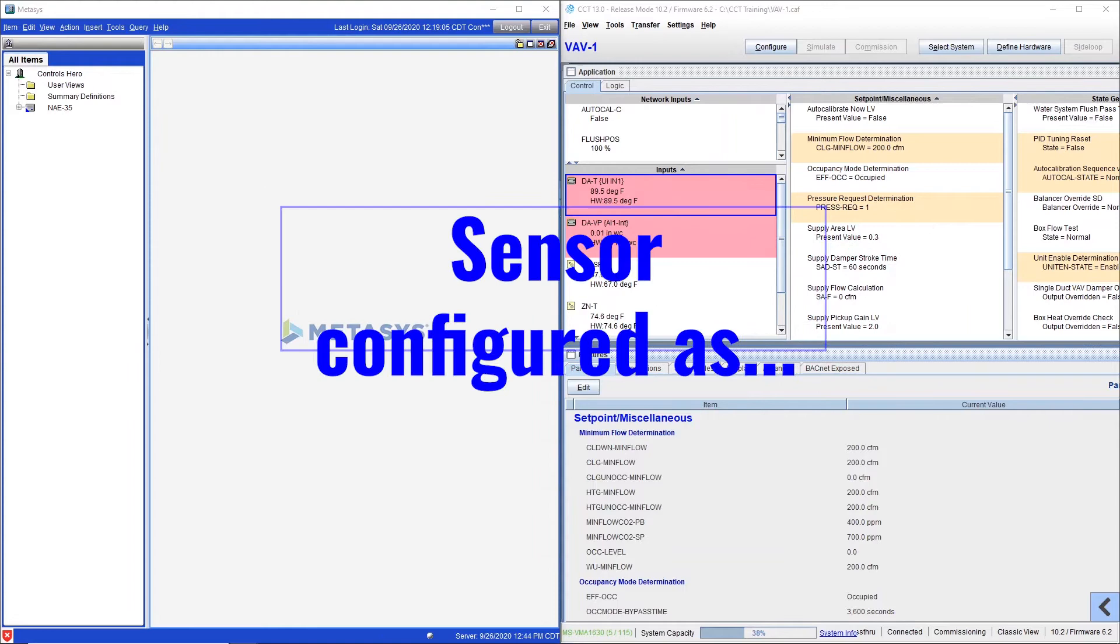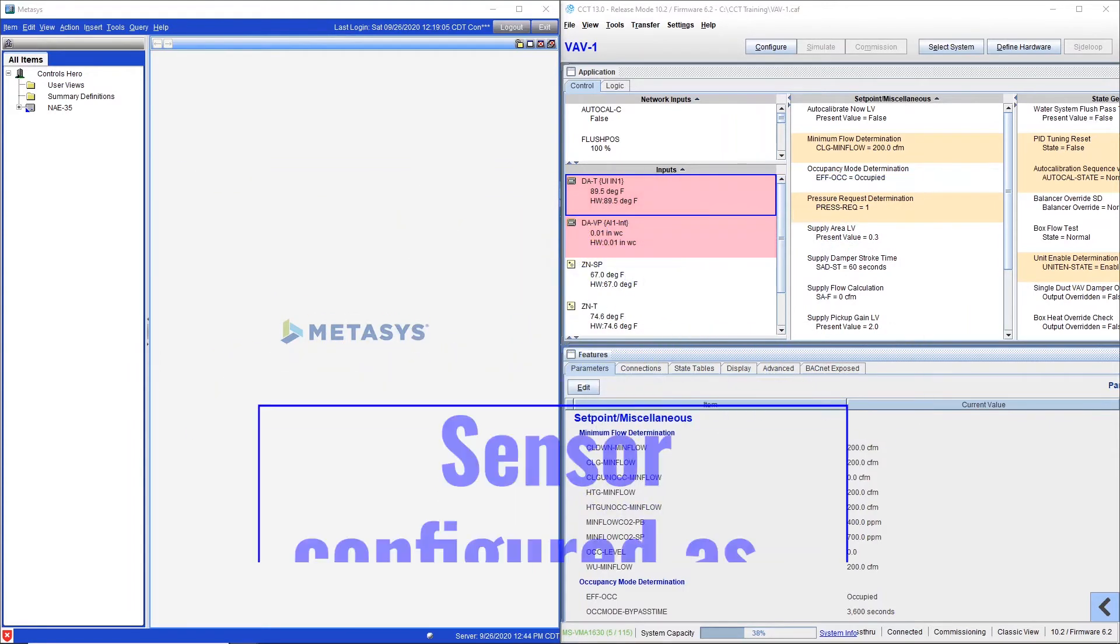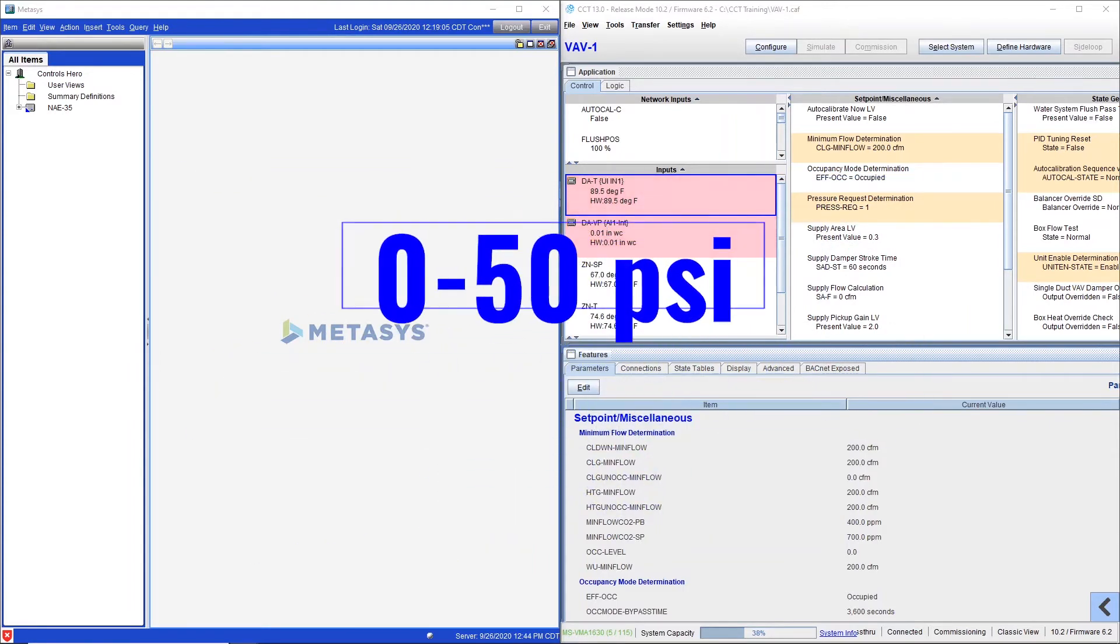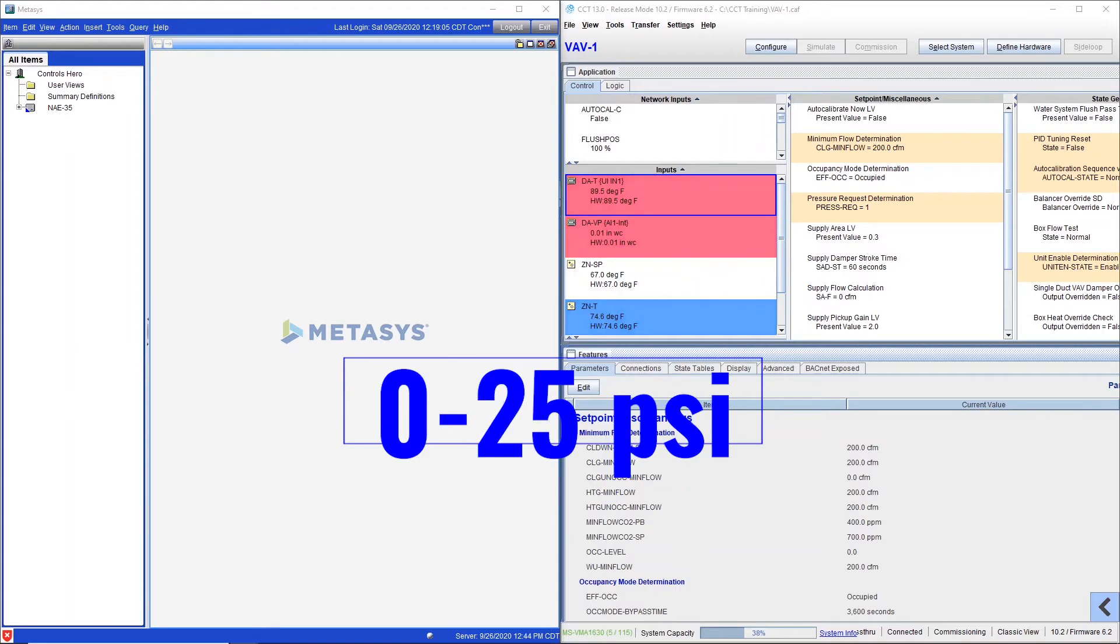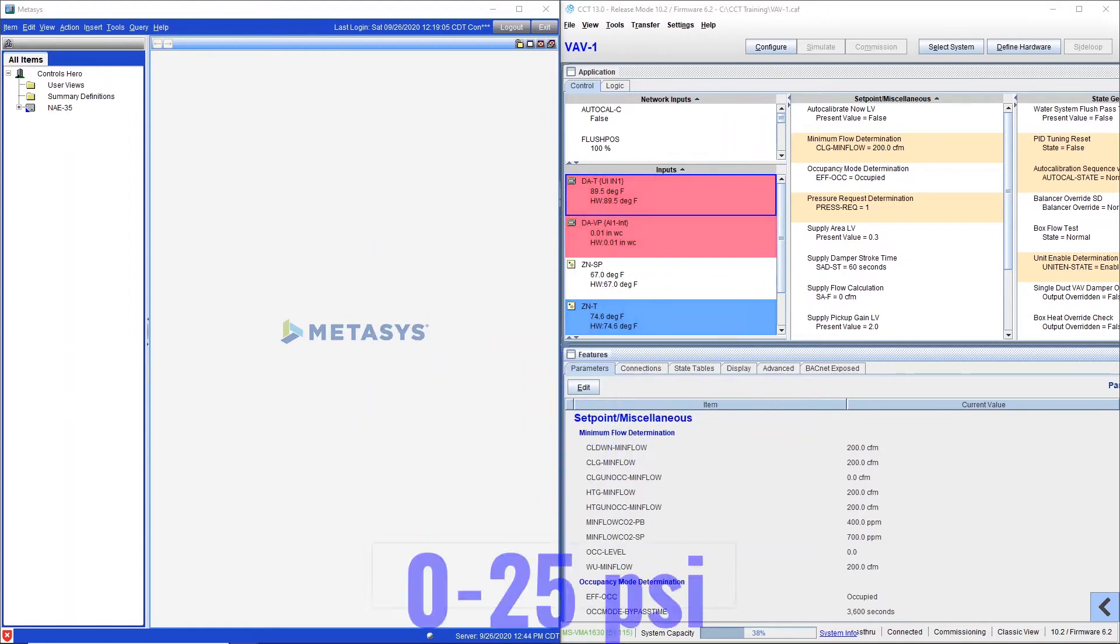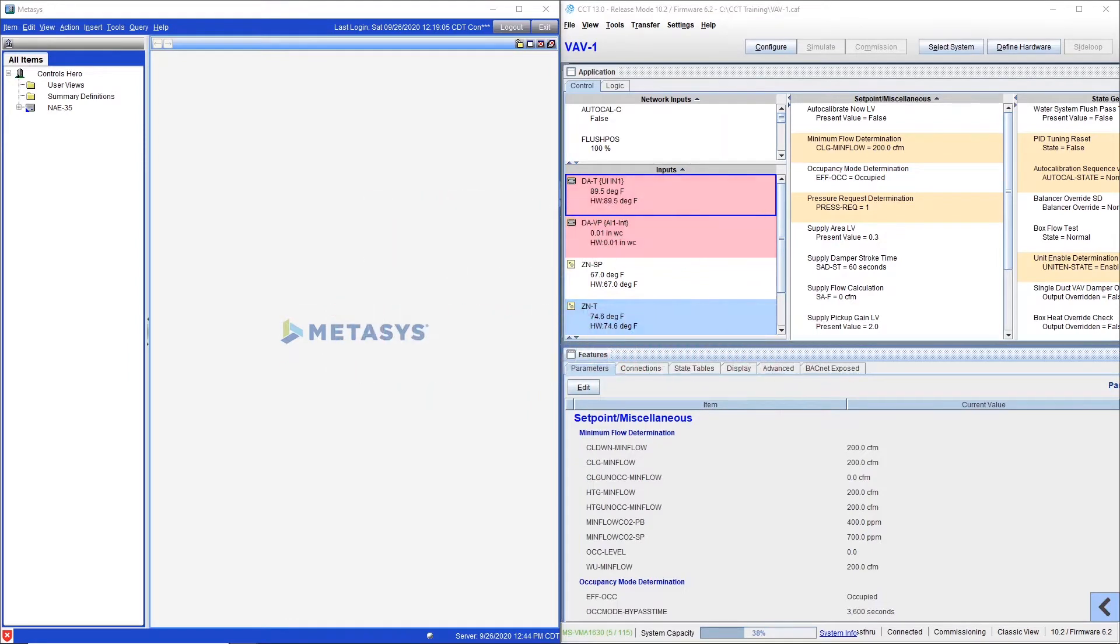For example, if you have a sensor that was configured as 0 to 50 psi but it's actually 0 to 25 psi, well good news you can do all this within Metasys without even opening CCT, the controller configuration tool.